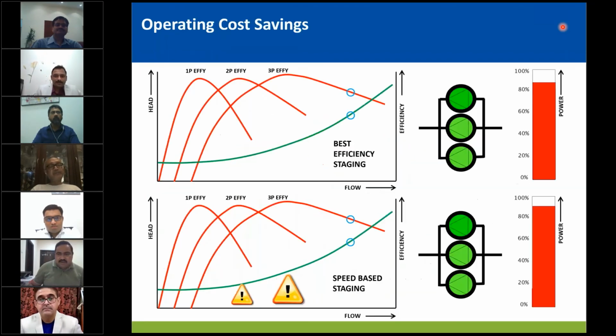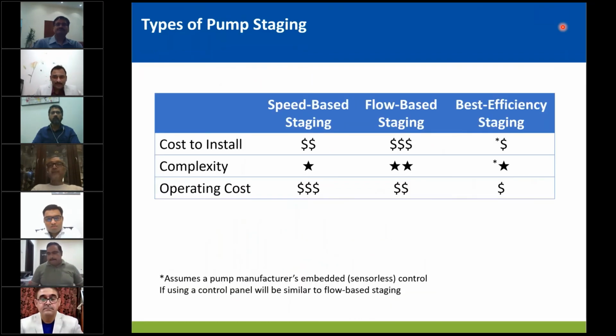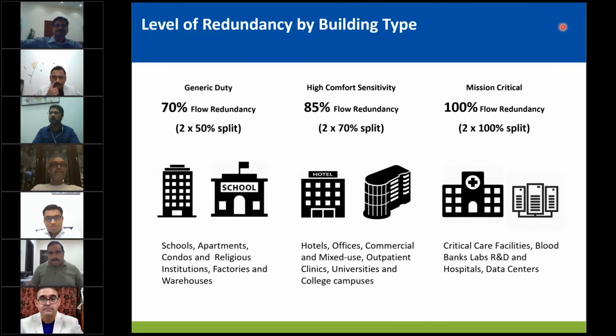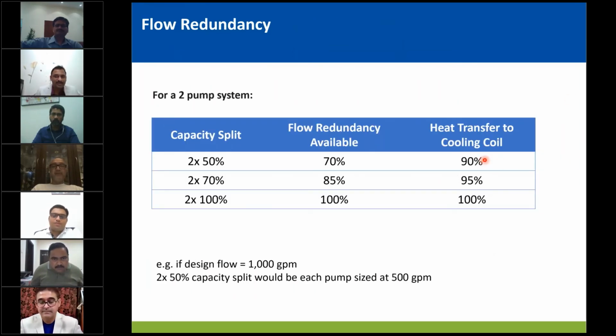Okay, so I'll go back to that slide. So based on the applications, the generic duty, it's good to have a 2 into 50% split. You still have 70% flow redundancy, and you have 90% heat transfer capacity to the building.